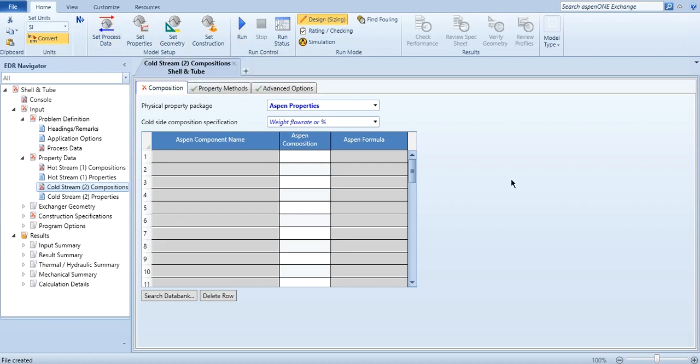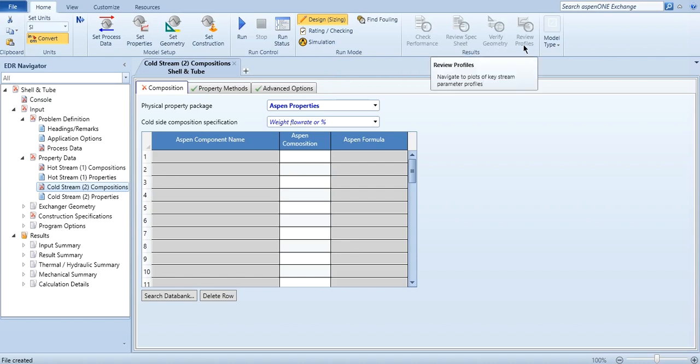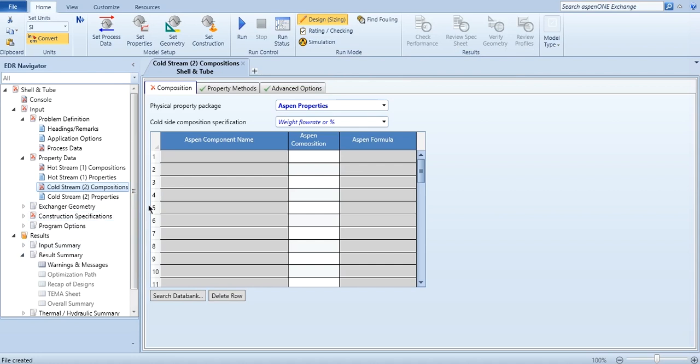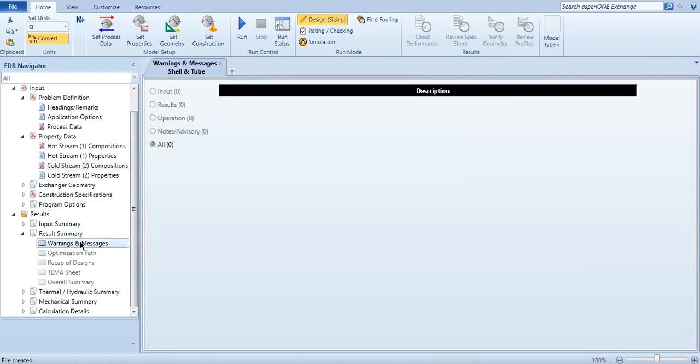And once after running, what you do, you have to check the performance. Like from here you can check the performance, you can check the spec sheet, you can verify the geometry, you can review the different profiles. Like in result summary you can see, you can even get different warnings and messages over here. Like for example, as you know, the by default location of hot fluid is in shell side, but it could be problematic as detected by it, so you can change it over here. Similarly, if you haven't specified pressure drop, it will give you a warning. If you haven't specified the fouling resistance, it will give you warnings.